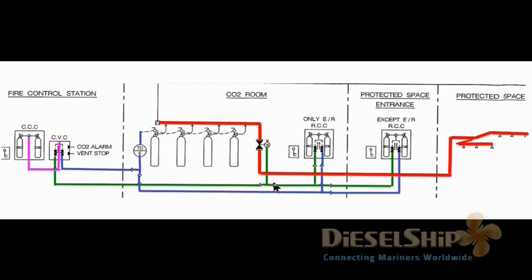There is a non-return valve here so the gas from the pilot cylinder can only pass one way — it cannot return, and it cannot go to the other valve control stations. The green line opens the main distribution valve. The blue line goes through a check valve and a time delay unit to open the main CO2 bottles in the CO2 room. As CO2 is released, following the red line through the distribution valve, it goes out to the engine room and the engine room space is flooded.